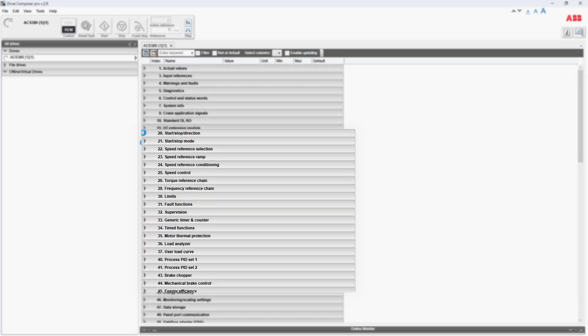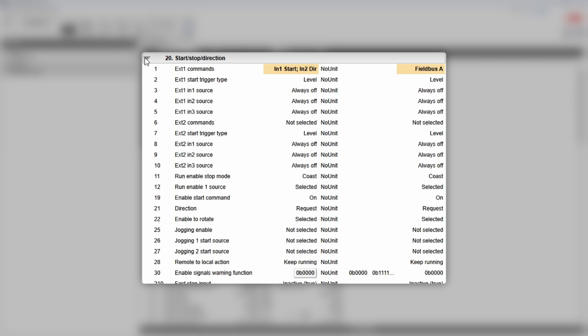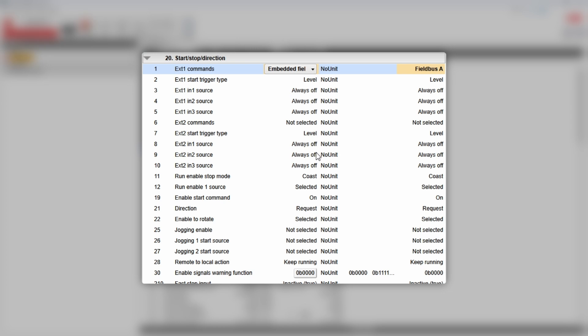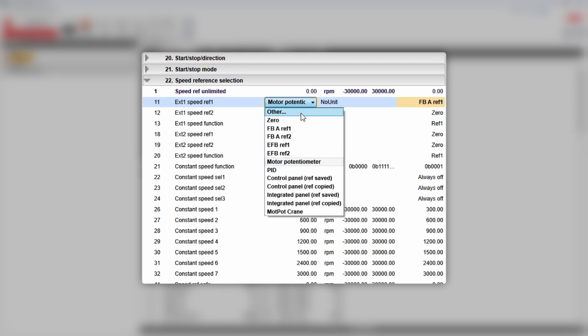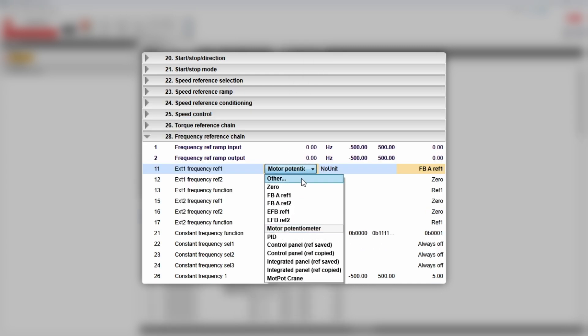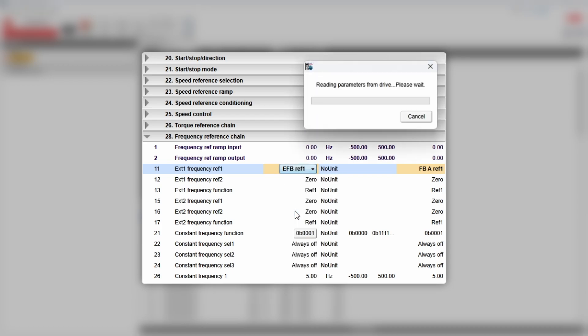Back to drive configuration. We need to make sure that control and reference locations are set to embedded fieldbus. Set parameter 2001 to embedded fieldbus, parameter 2211 to EFB ref1, and finally parameter 2811 to EFB ref1 as well.